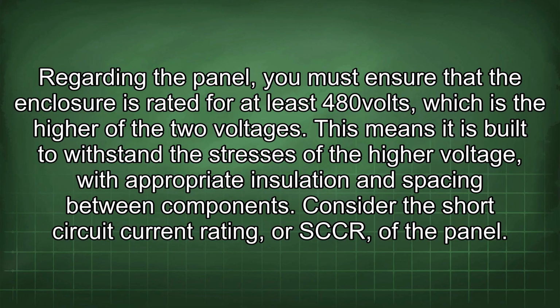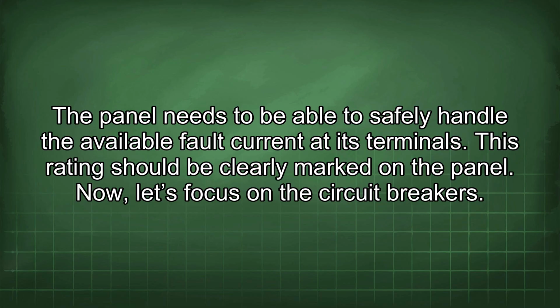Regarding the panel, you must ensure that the enclosure is rated for at least 480 volts, which is the higher of the two voltages. This means it is built to withstand the stresses of the higher voltage with appropriate insulation and spacing between components. Consider the short circuit current rating, or SCCR, of the panel. The panel needs to be able to safely handle the available fault current at its terminals. This rating should be clearly marked in the panel.